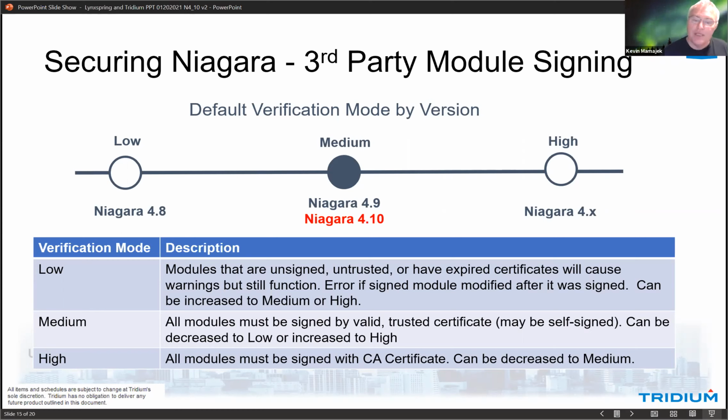What's that mean? It means that we actually have a special certificate around each module so that when Niagara starts up, it verifies that those code signing certificates are still valid and nobody's tampered with any of that code. So what's happening is we're asking, and we're giving plenty of time, our third party driver creators to actually start to sign their code. And so there's a whole method that's there.